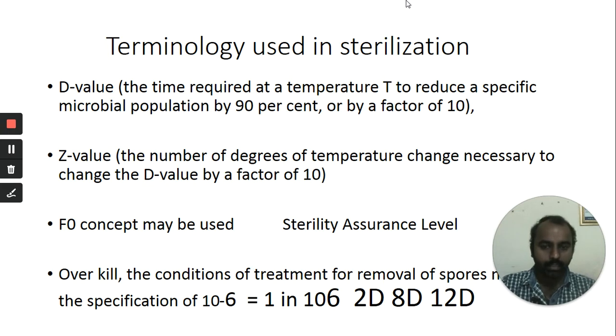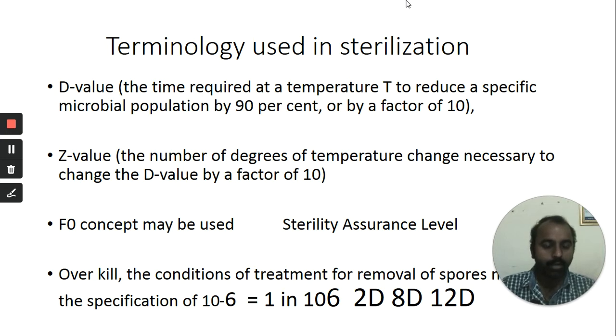The Z value is the number of degrees of temperature change that will change the D value by a factor of 10. The Z value precisely determines how well your sterilization cycle is accelerated. The F0 concept is the next important parameter to understand.